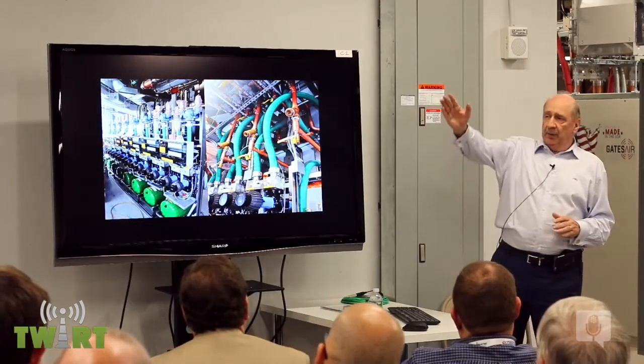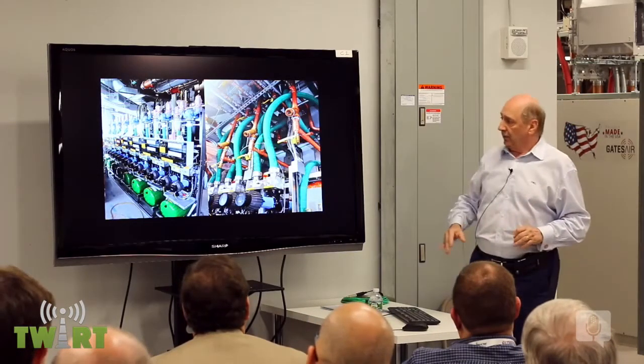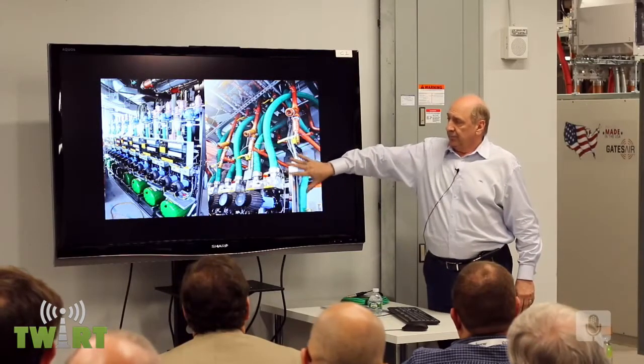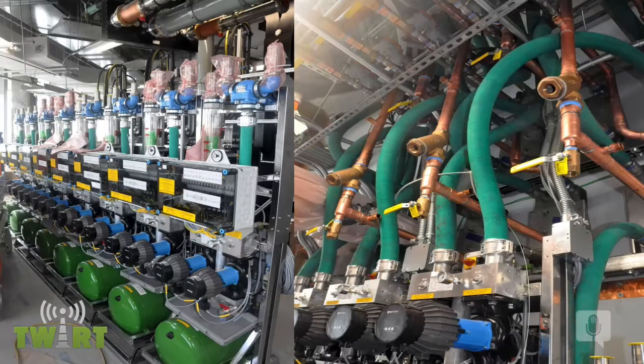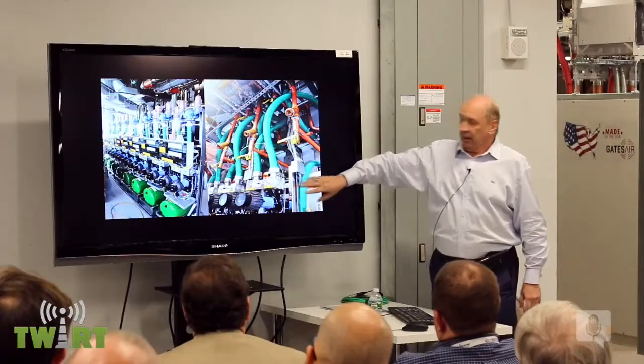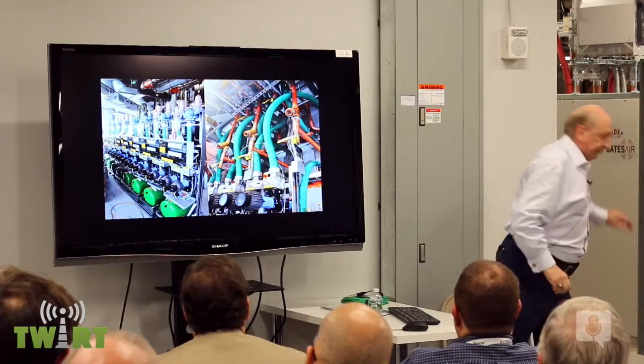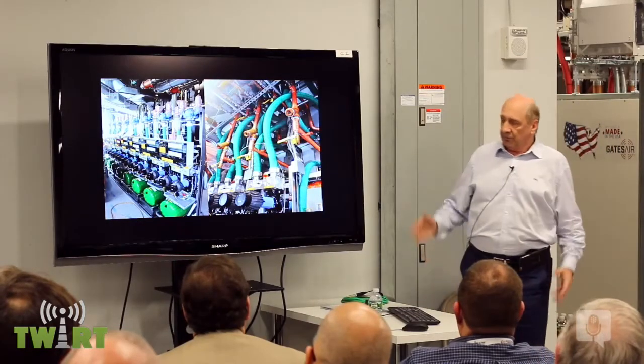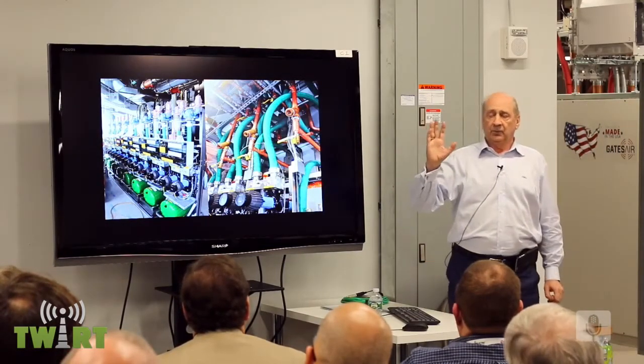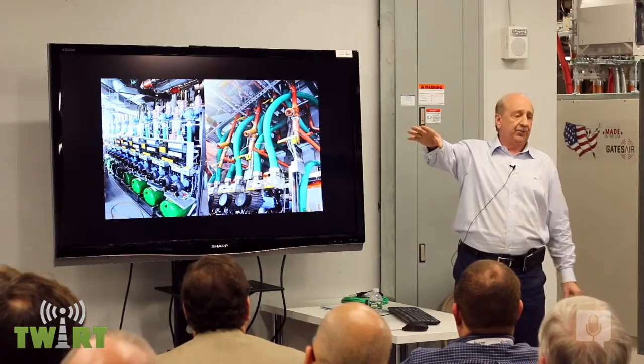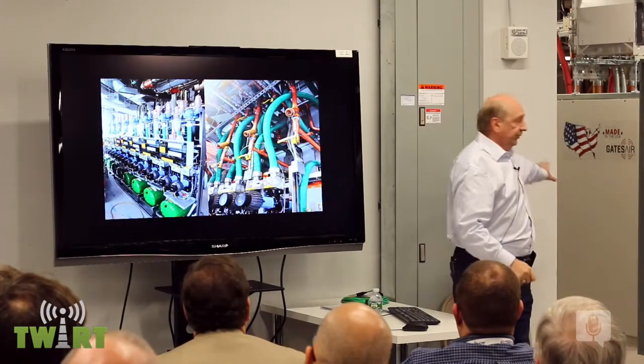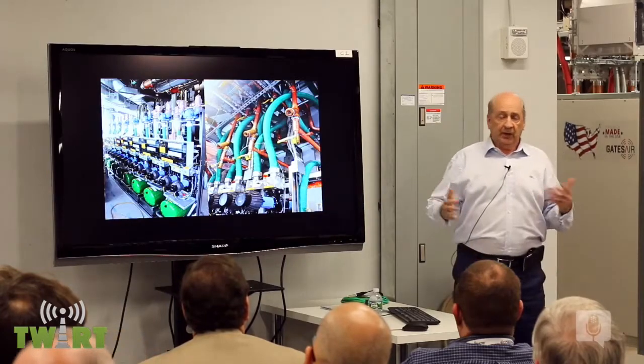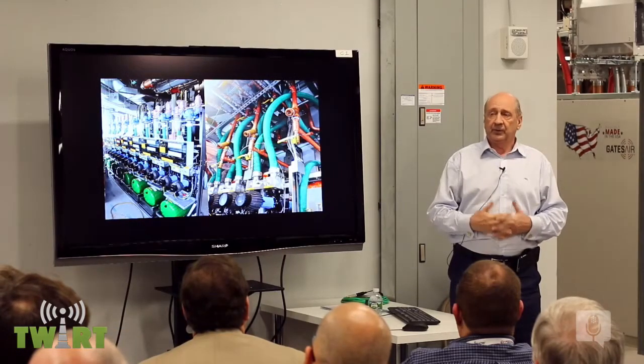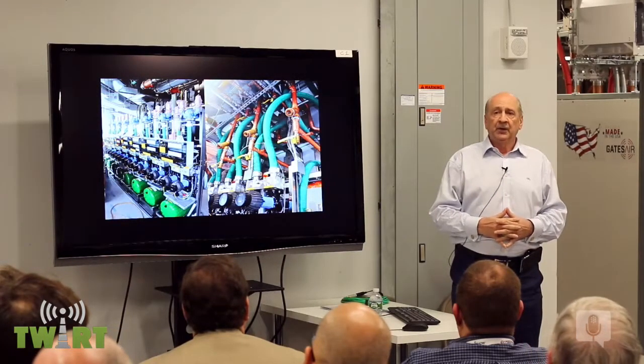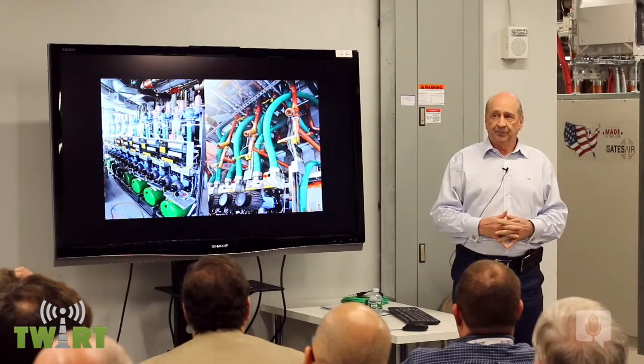I'm going to go around some of the other facilities being green. This is what you're looking at behind here. These are the pumps from the combiner, which is on the other side of the floor. And Gates has slightly different pumps in the CBS area over here. But essentially, they're the same. They're pumping glycol water mix. They're doing 39% glycol, 61% water. They're doing 50-50. Different philosophies in the two different companies, but essentially it's a glycol loop to help with the cooling. Transmitters are all water cooled up here.